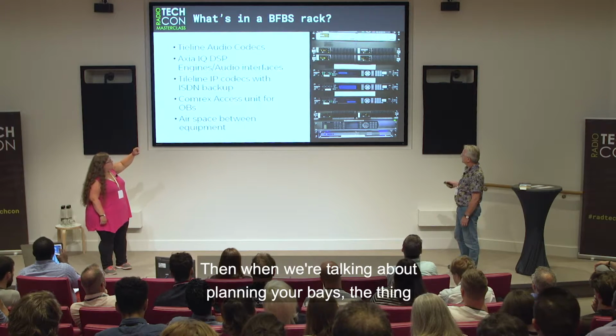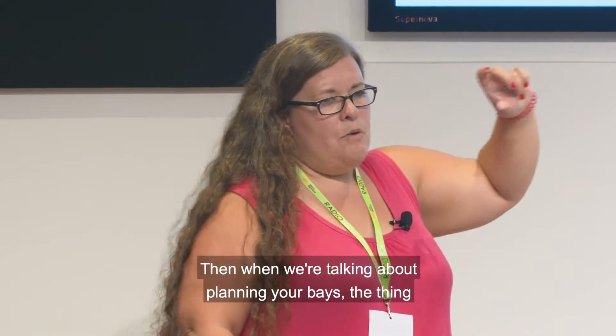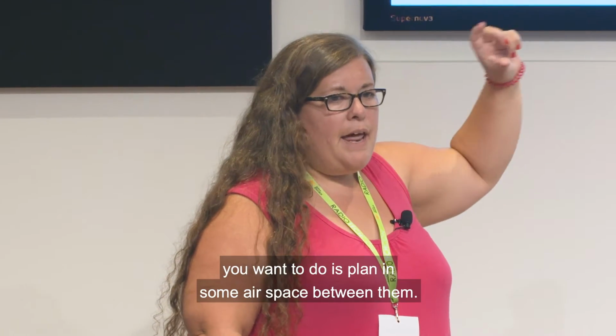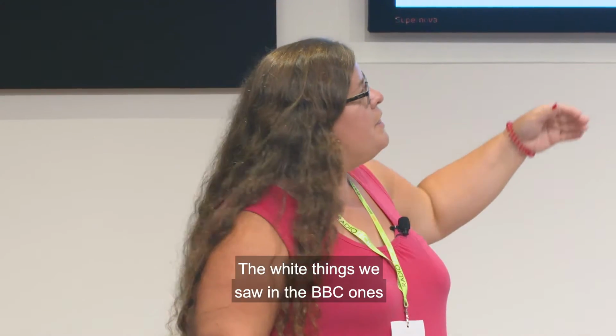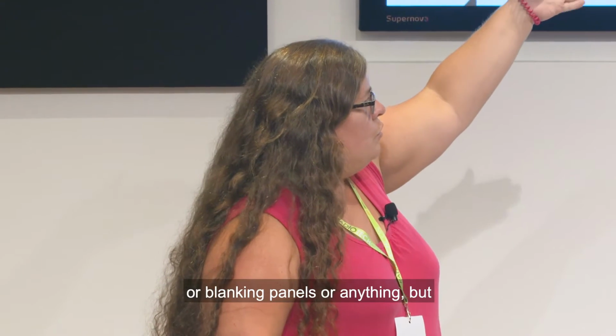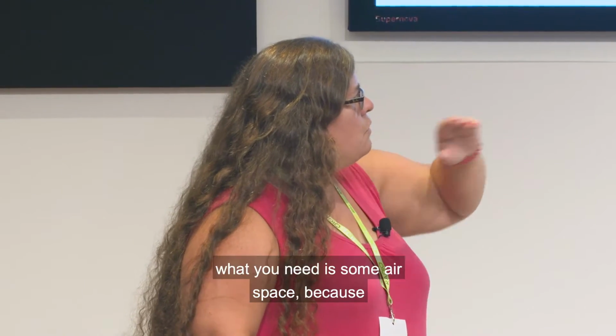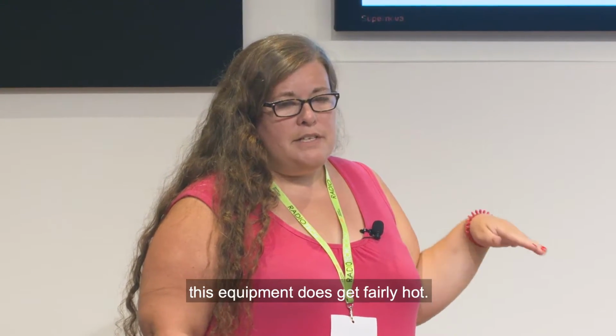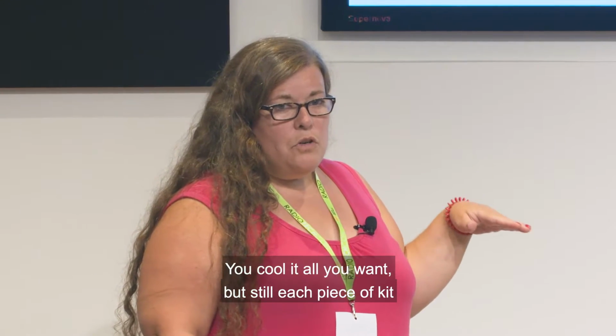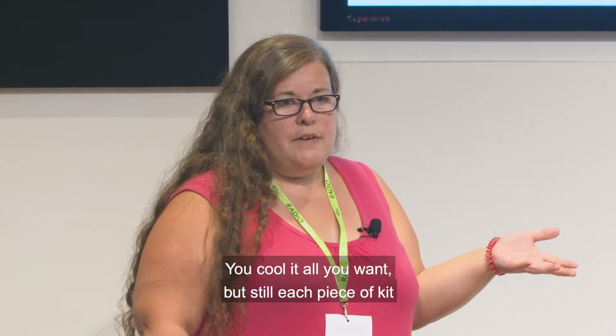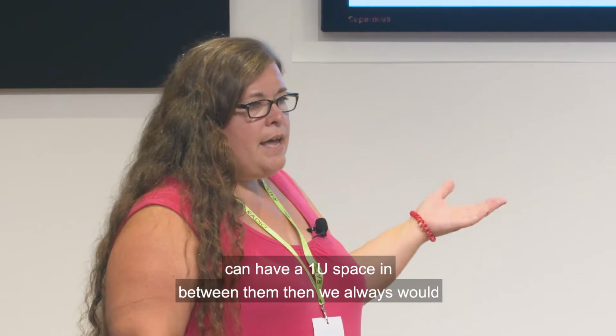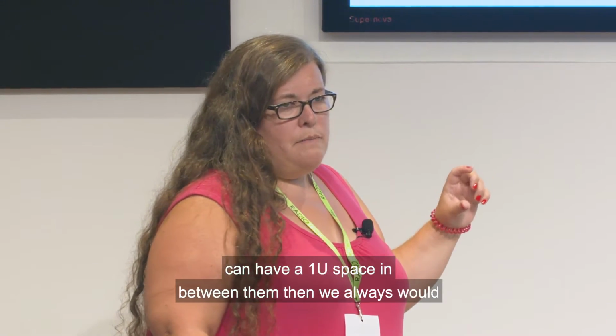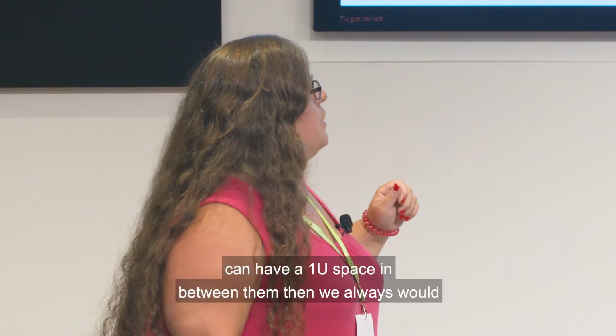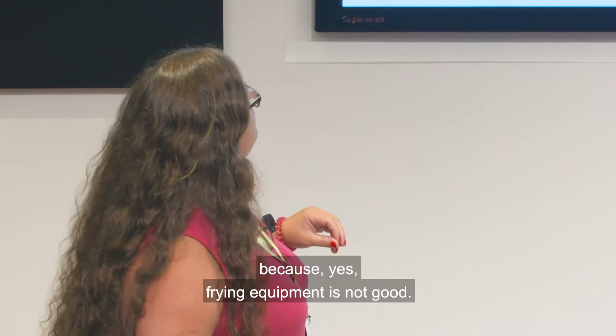When planning your bays, you want to plan in some airspace between them. The white things we saw in the BBC ones are blanking panels, but what you need is airspace because this equipment gets fairly hot. You can cool it all you want, but each piece of kit still has residual heat, so if we can have a one-unit space in between them, we always would - frying equipment is not good.